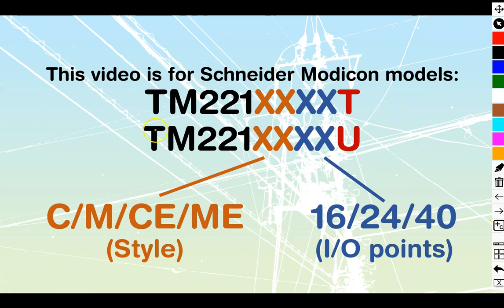Take a look at the part number of the PLC you have in front of you. You are looking for a T, or you are looking for a U at the very end. All of these Modicons in this family are going to have a TM221 at the very beginning. Then they're going to have one or two letters in this range over here, which is going to be C, M, CE, or ME, which will tell you if it's cartridge, monolithic, or Ethernet enabled. And then you're going to have the total number of I/O points, which will be listed next, 16, 24, or 40. For this video, though, what we're looking for is it has to have these.